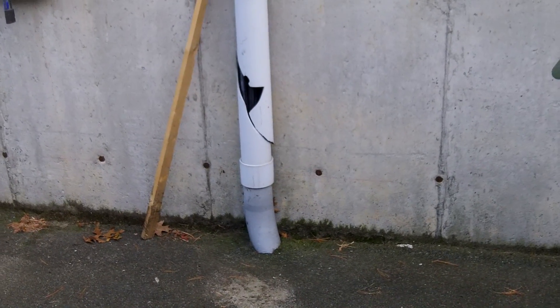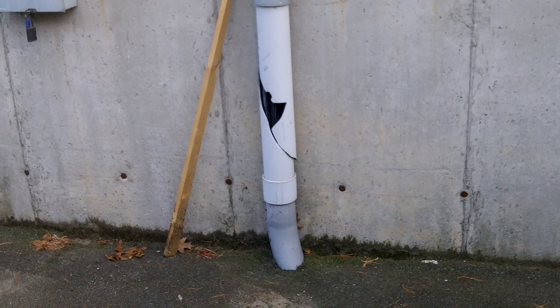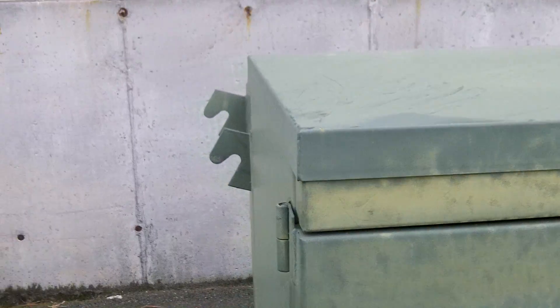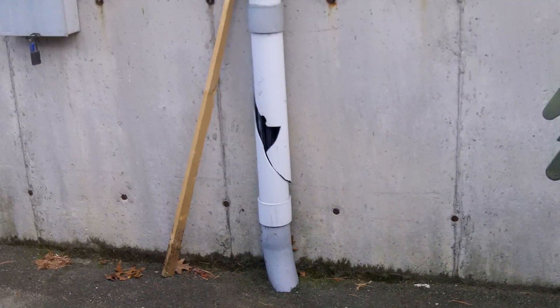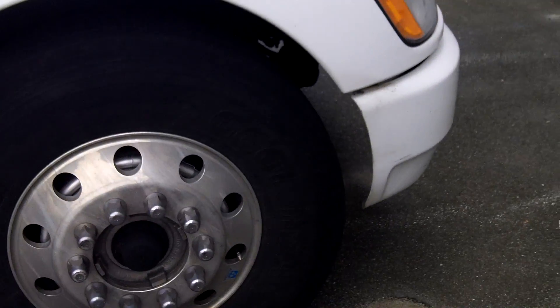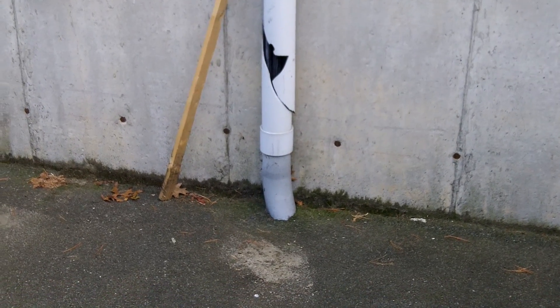I'm taking a look at this broken PVC pipe we see here. This is for underground service conductors which come from this pad-mount transformer right next to me. This area is also subject to vehicle traffic — there's a truck right here.